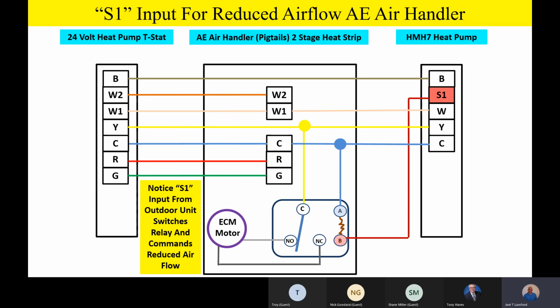Now remember, on the normally open contact, we want to be around 60% airflow. So select an airflow that's going to give you about 60% airflow whenever we get that S1 input from the outdoor unit. Any questions or comments on that little animation and how that relay is working to reduce airflow when the outdoor unit commands it? Make sense? All right, well, let's continue with our training then.